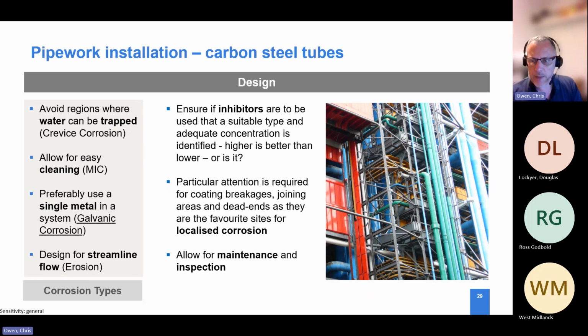Whilst inhibitors can be used as a means of mitigating the risk of corrosion, some of the evidence we've seen shows that correct use of inhibitor, making sure it's the right quantity and circulated right through the system, can be a bit of a challenge, which gives people a false sense of security. We've dosed the system, we've got an inhibitor in, so it must be okay. But if it's the wrong inhibitor, wrong strength, or not getting around the system, you can have other issues which cause corrosion.